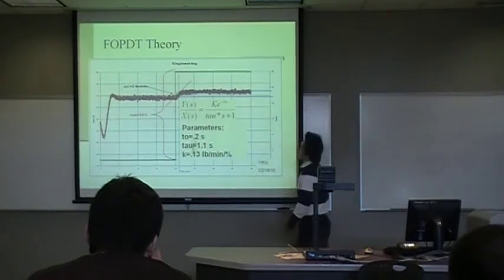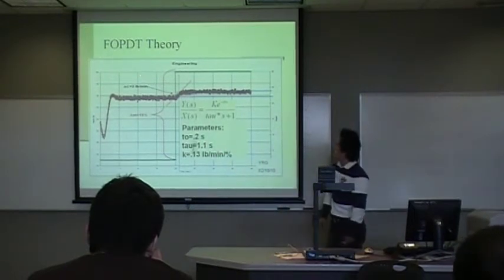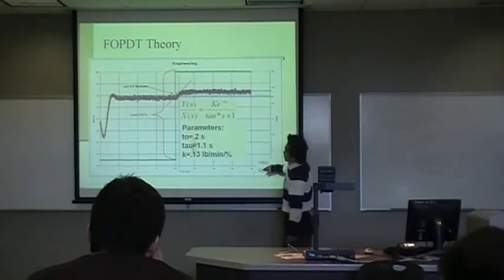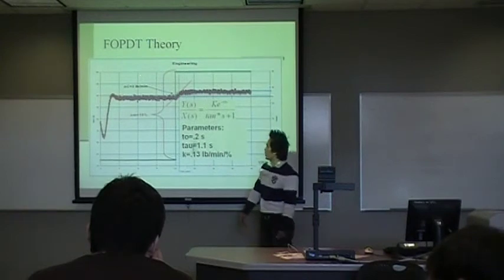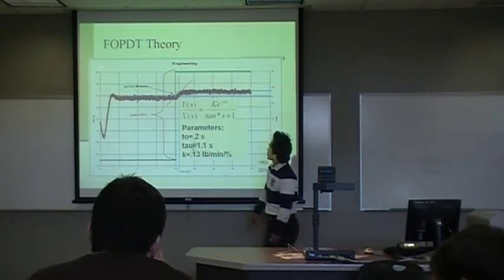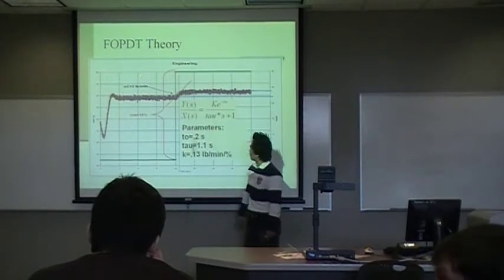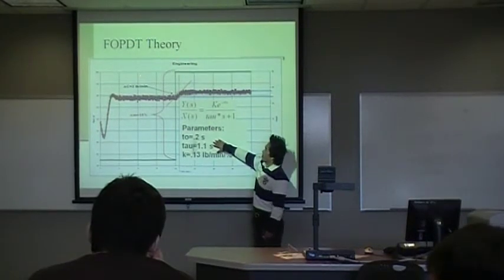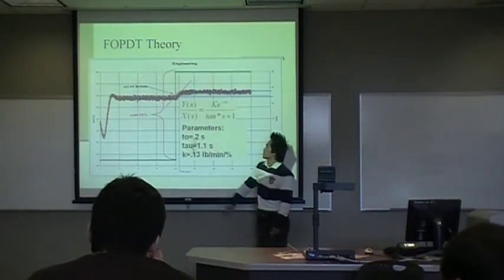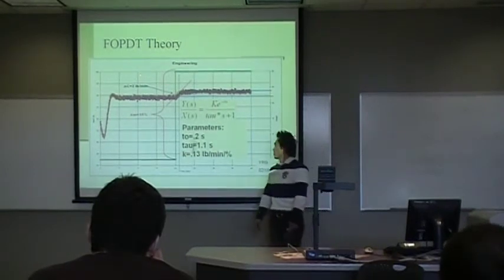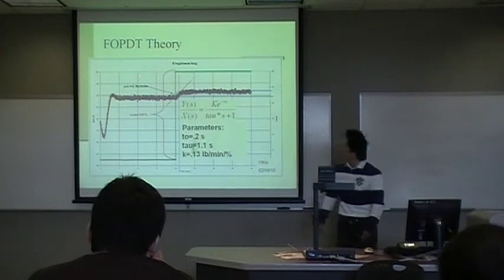We use the IPOM method to find those parameters. In this graph we have input 85% with an increase of 50%, and we use the IPOM method to find T0 is 0.2 seconds, Tau is 1.1 seconds, and K is 0.13 lb per minute per percent.